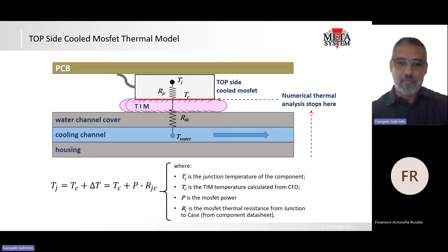Why do we expect derating? Because we are exceeding the maximum temperature allowed by the MOSFET components. If the MOSFET junction has a maximum allowed temperature of typically 175 degrees, we keep a margin of about 25 degrees, so our maximum temperature would be 150.